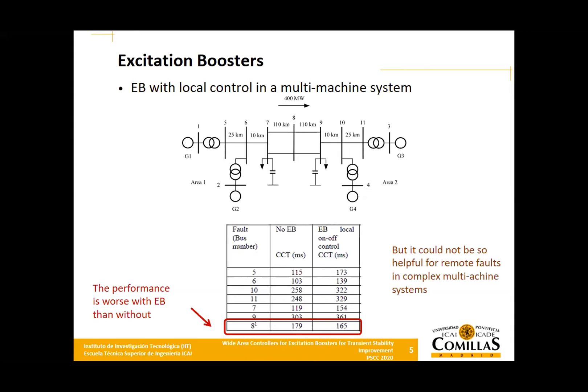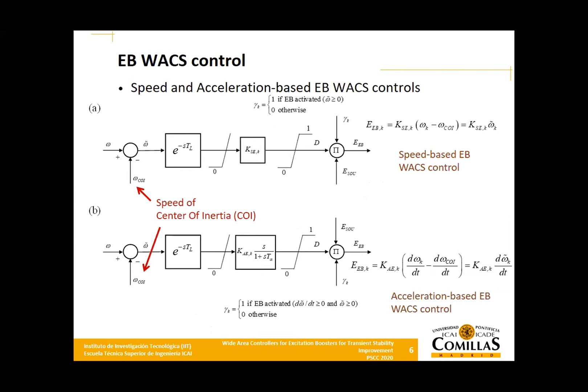However, for a remote fault — in this case at the midpoint of the two-area test system developed by Kundur — adding an excitation booster to all generators results in worse performance, lower critical clearing time than without the excitation booster. Having learned of this phenomenon, we proposed a wide area control system based on either speed or acceleration, where the input signal is the speed deviation of the generator with respect to the center of inertia.